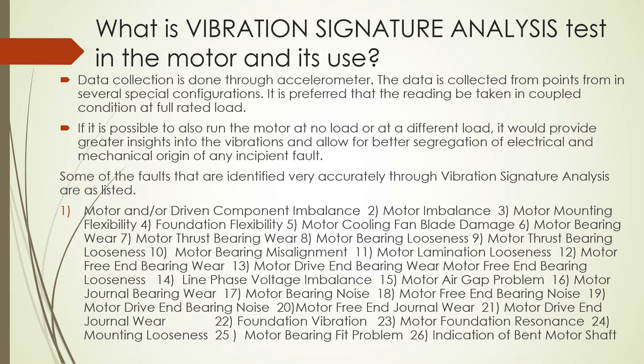The sixth question: what is vibration signature analysis for a motor and its use? Data collection is done through an accelerometer. Data is collected from several points in special configurations. It is preferred that readings be taken in a coupled condition at full rated load if possible. Running the motor at no load or at different loads provides greater insights into vibrations and allows for better segregation of electrical and mechanical origins of any incipient fault.